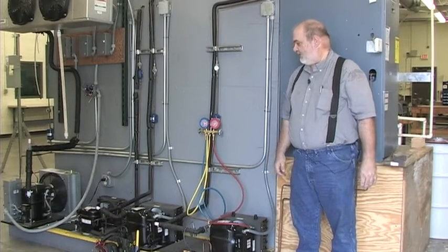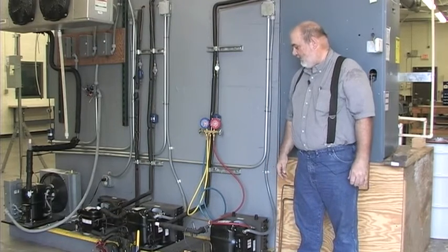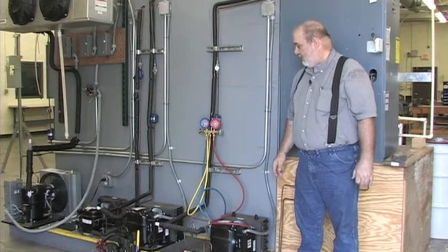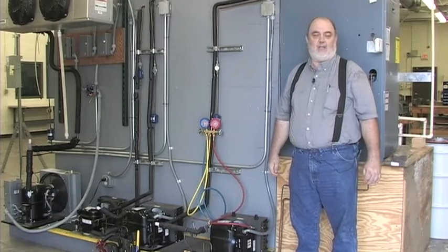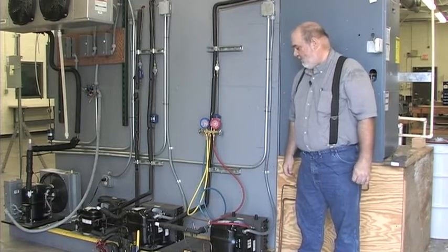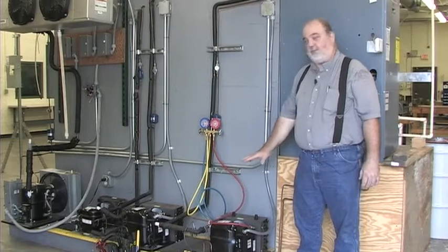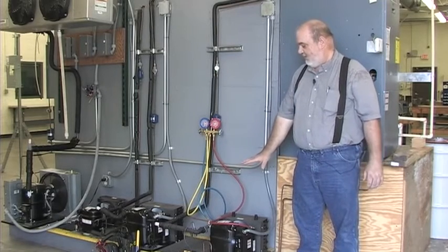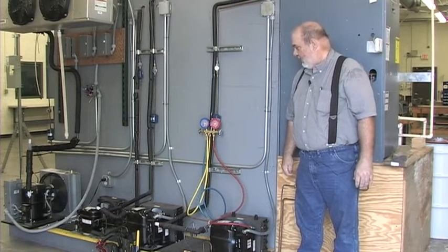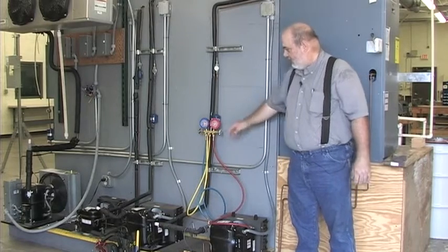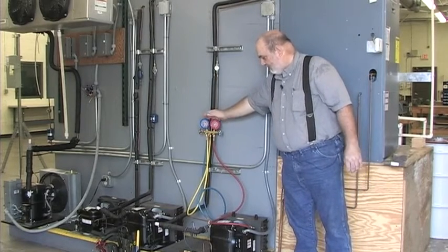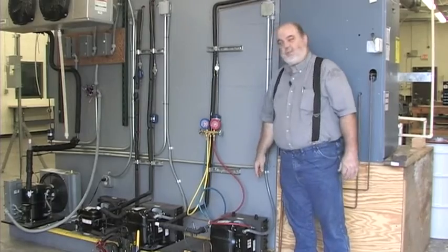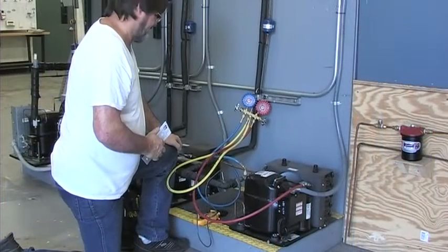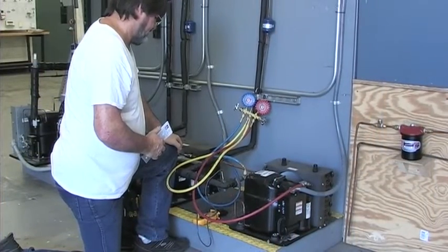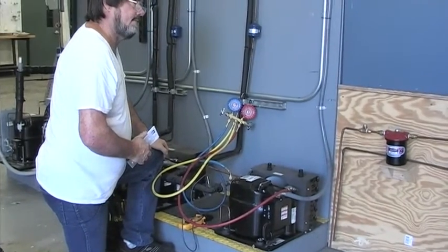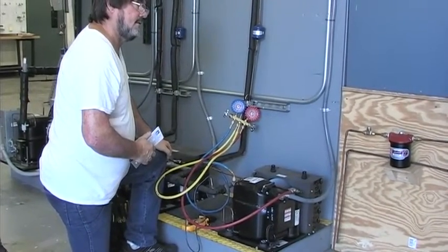Next, we're going to look at some refrigeration equipment we have here in the lab. What the student will be doing today is demonstrating how to calculate superheat. Superheat is very important in the refrigeration industry to protect your compressor, which is the major component in your refrigeration system. Carlos will now use the gauge manifold set and a thermometer to calculate superheat. Carlos is going to calculate the superheat for this low temperature refrigeration system that you would find in your local convenience store or at your supermarket.